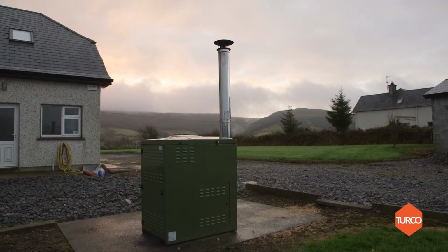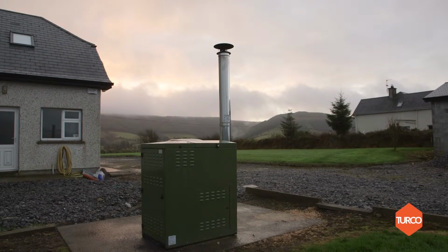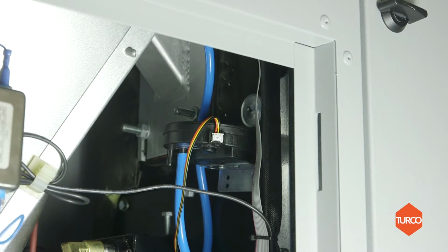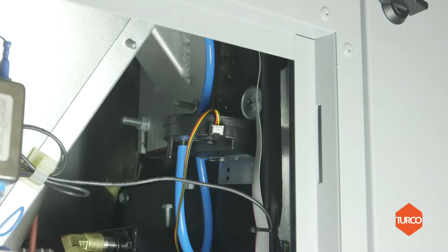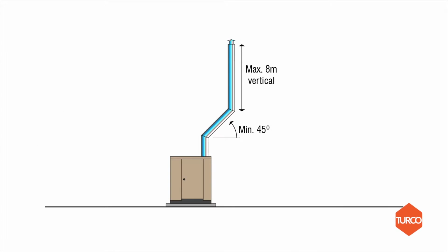Sometimes an anti-downdraft cowl or spinning cowl may be required. When commissioning, we will show you the importance of draft and how the vacuum regulator assists this. The flue pipe must not include any horizontal pipe runs. It is also advisable not to exceed 8 metres of vertical pipe.